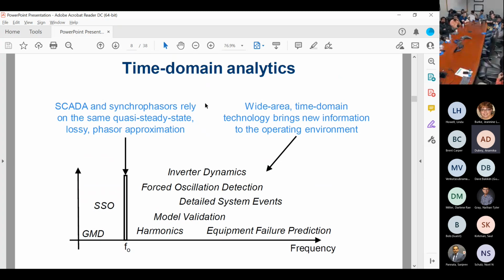Okay, so the other thing that we've done work on is what we call time domain. It's basically streaming samples, you can call it time domain, as opposed to phasors. So you all know about how phasors work, I'm assuming. When I think of a phasor, I think of it as a gigantic lossy data compression thing. I've got all this interesting power system information out there just waiting to be used for something. And then at the device, typically a blue box that we made, it provides a super narrow bandpass filter and just throws everything interesting away, right? You're stuck with the phasor, magnitude and angle, right?